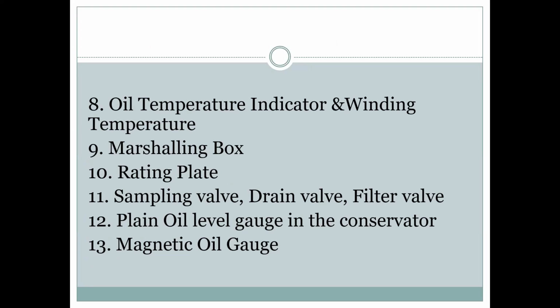So the setting is done for alarm and trip purposes. It gives you an alarm. You have to attend to it, the way the temperature is going up suddenly, and rectify that fault if possible, or the transformer will give a tripping signal. Then the transformer will stop. It will de-energize from the circuit, because basically the requirement is that the transformer is the heart of power. Power shutdown at any cost is not acceptable.